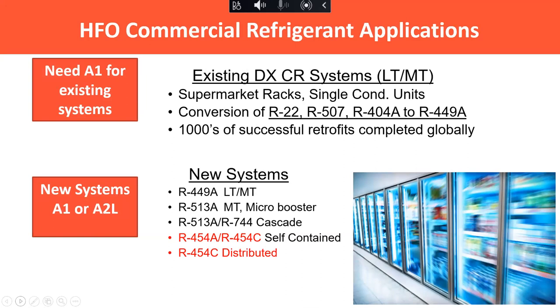Looking at commercial refrigerants, where things like 407, 404, 507, even a lot of R22 were used traditionally, I want to be clear that there's going to be a need for A1 non-flammable refrigerants to service, retrofit, or convert a lot of that equipment that's still going to be running for a long time. That still has to be non-flammable. If it was designed for non-flammable, it's got to have non-flammable refrigerants. So there are lower GWP refrigerants, 449A, 448, as examples, that are going into a lot of existing systems.